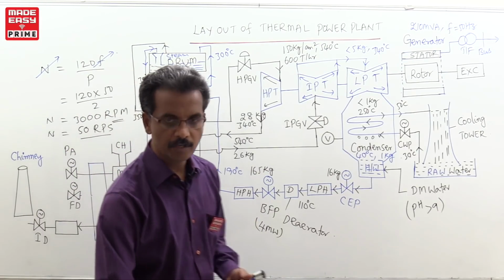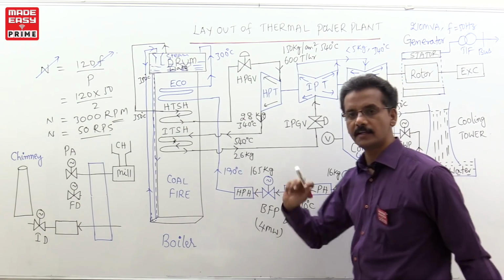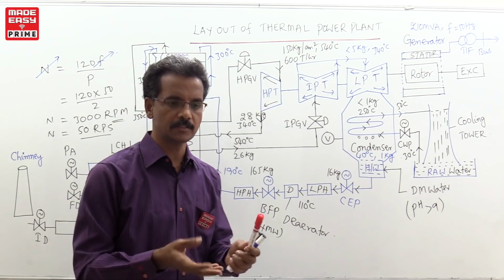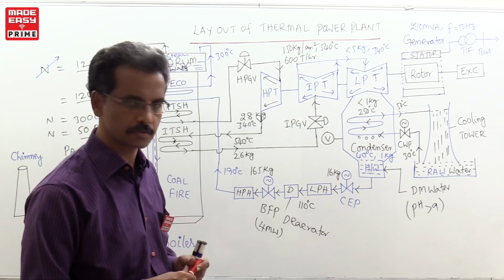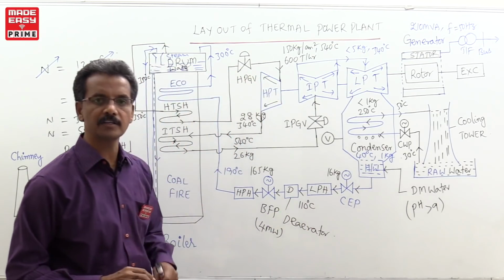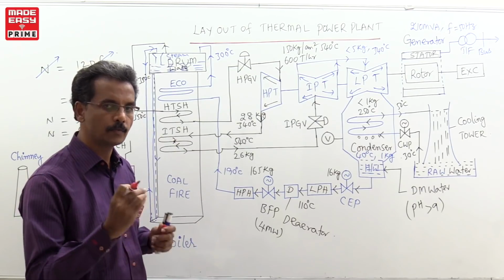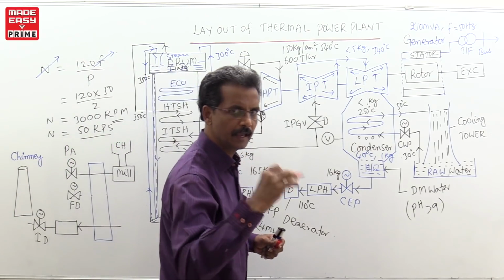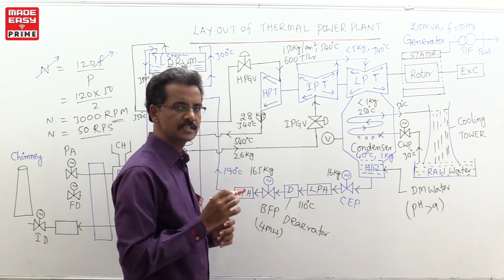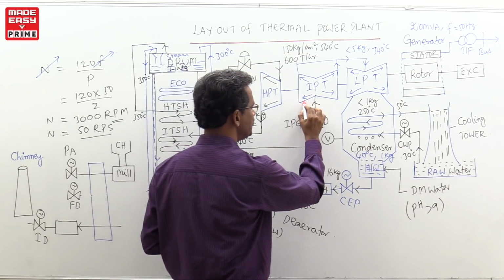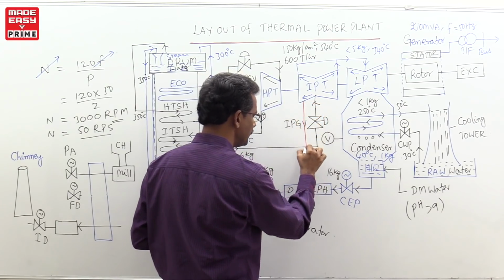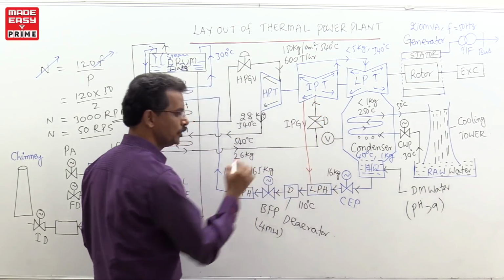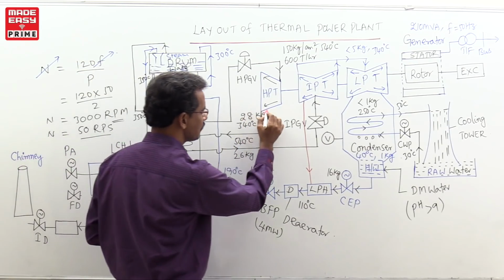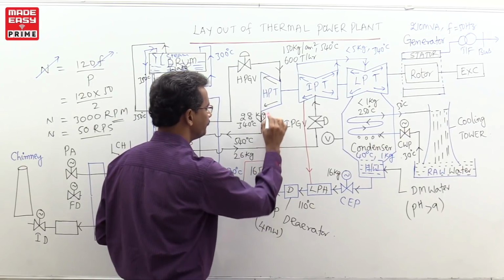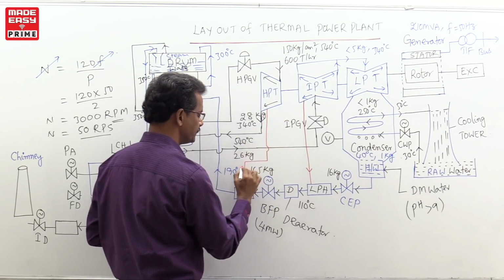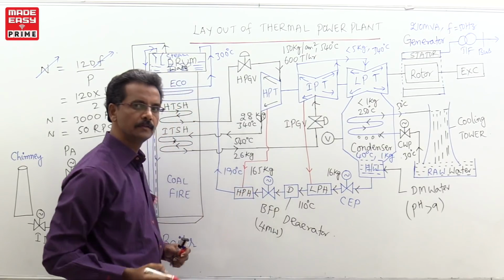Remember one more point here. What is the meaning of these heaters, LP heaters and HP heaters? These are not electrical heaters, like the immersion heater you use in a house. These are steam heaters. LP heaters and HP heaters are steam heaters. How it works is one of the important areas when calculating the efficiency of the turbines and all. From one of the stages of the LP turbine, they take the steam, and that steam is admitted into the LP heaters, and from one of the stages of the HP turbine, they take steam, and that steam enters into the HP heaters.